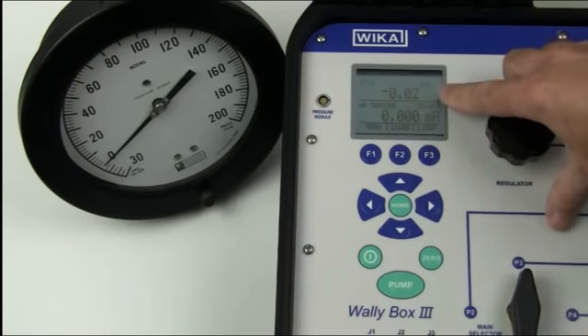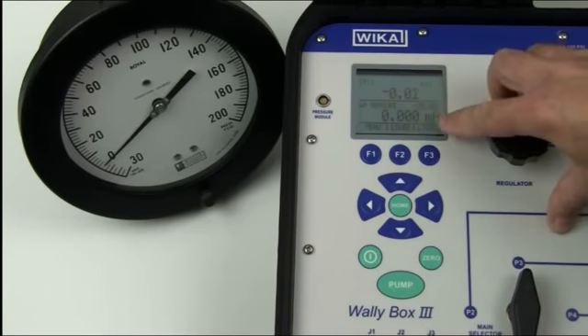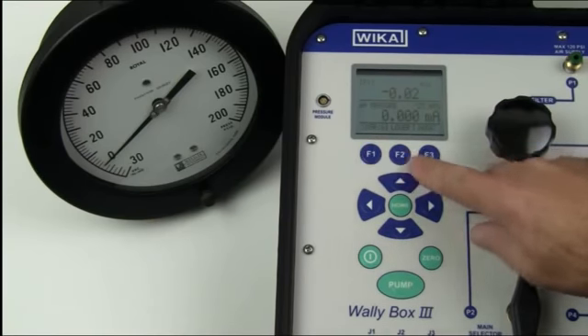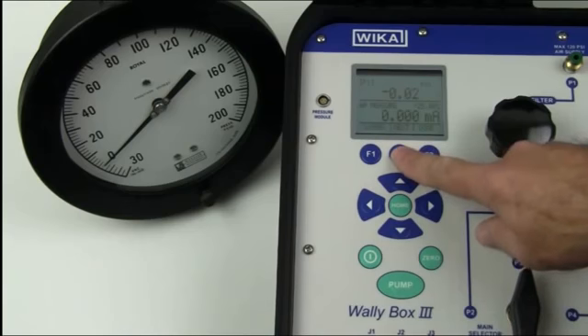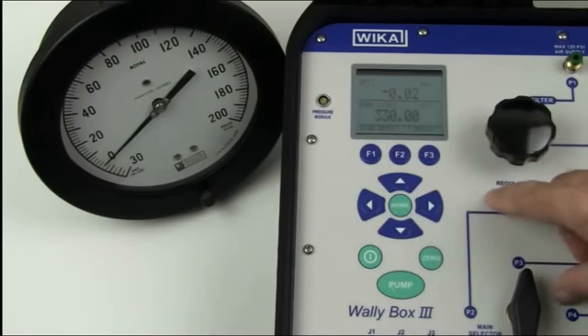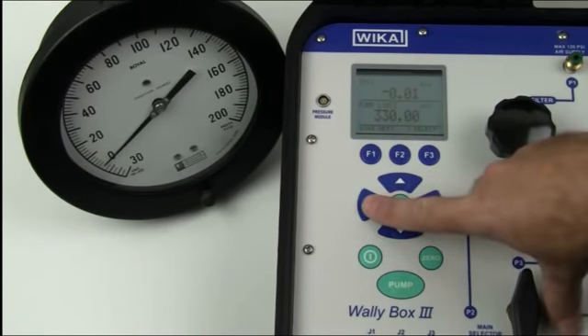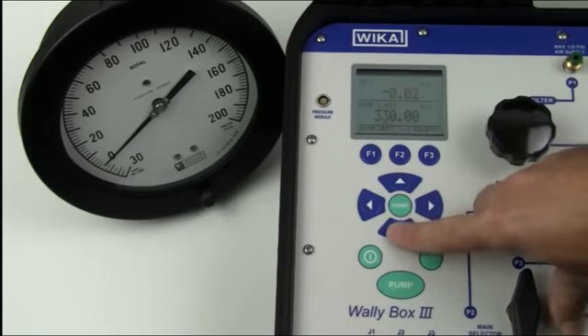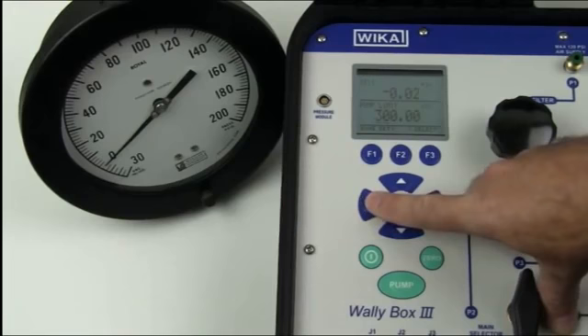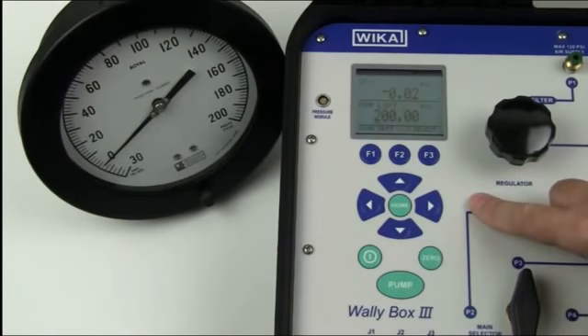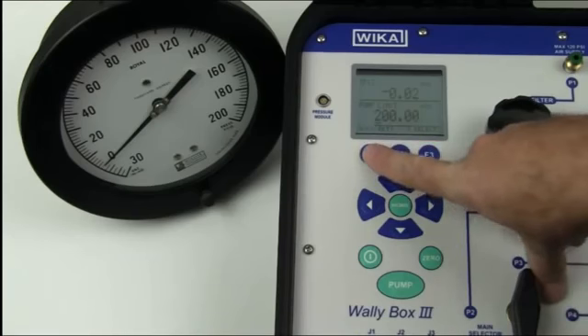Now our display will indicate the internal pressure, where we generate the pressure from our pump, and the bottom display will indicate what we're doing with the pump. So we'll go across to the menu, we'll go to more, and we'll keep choosing next until we come to the pump. The reason why we're doing this with the pump is that the pump can go up to 330 psi, but the gauge only goes to 200. So with using the arrow keys, we select and we reduce the reading so that the pump will not exceed that of the gauge of 200 psi.